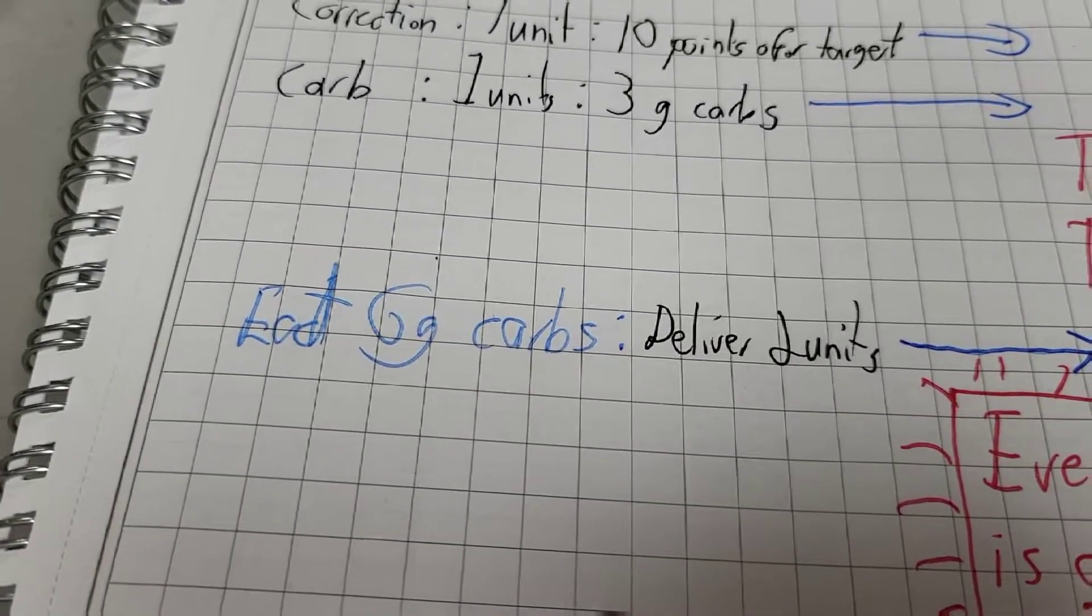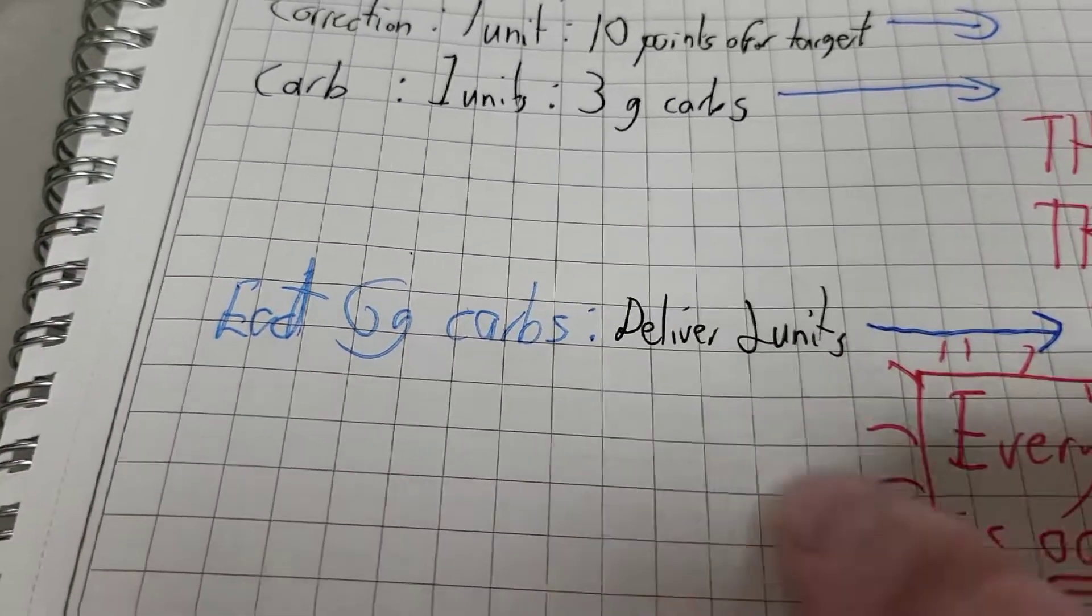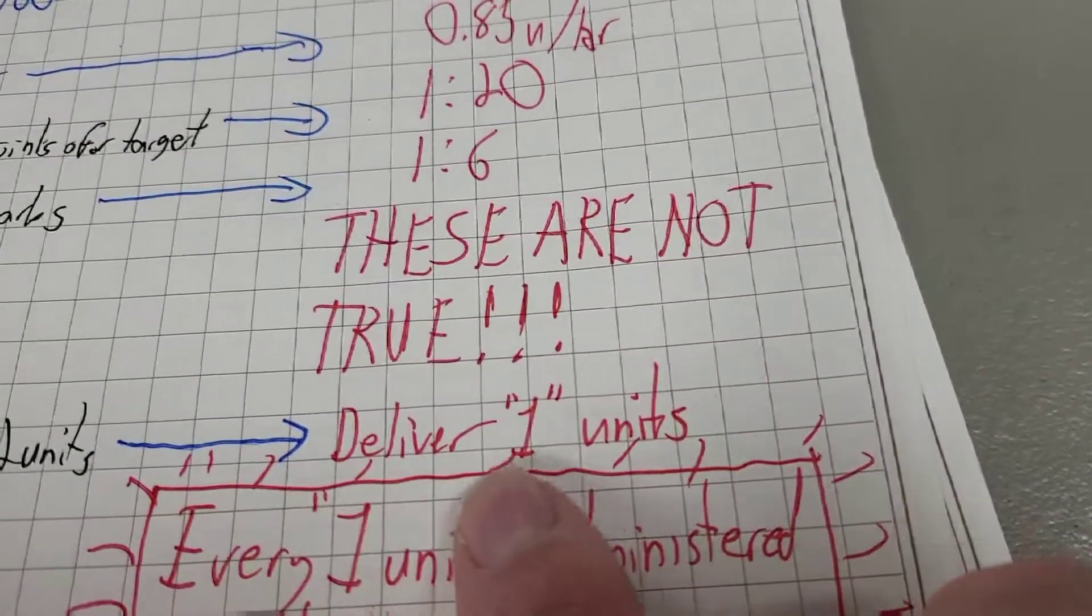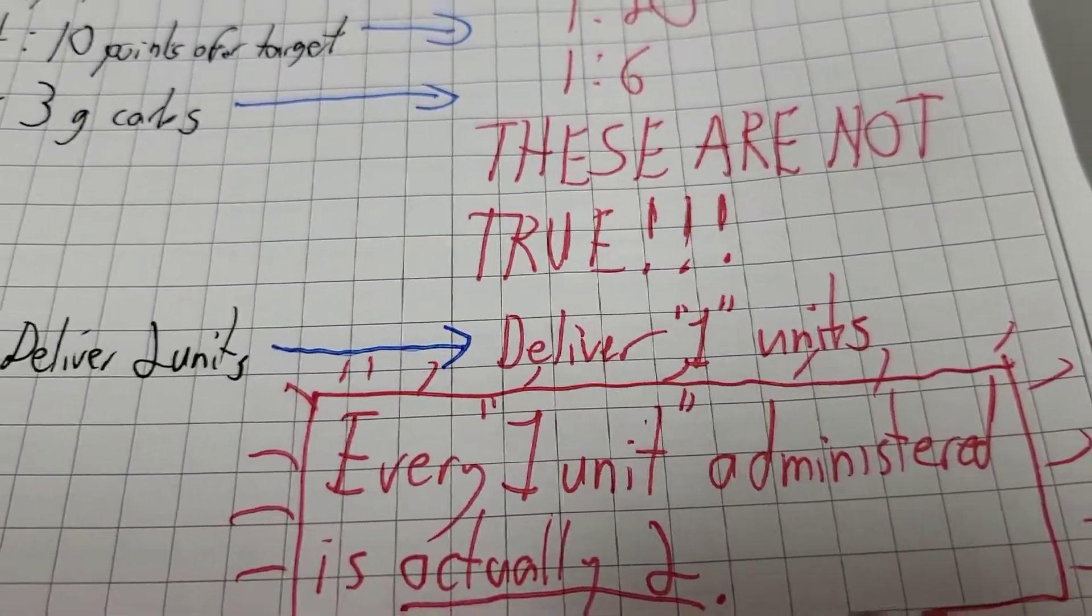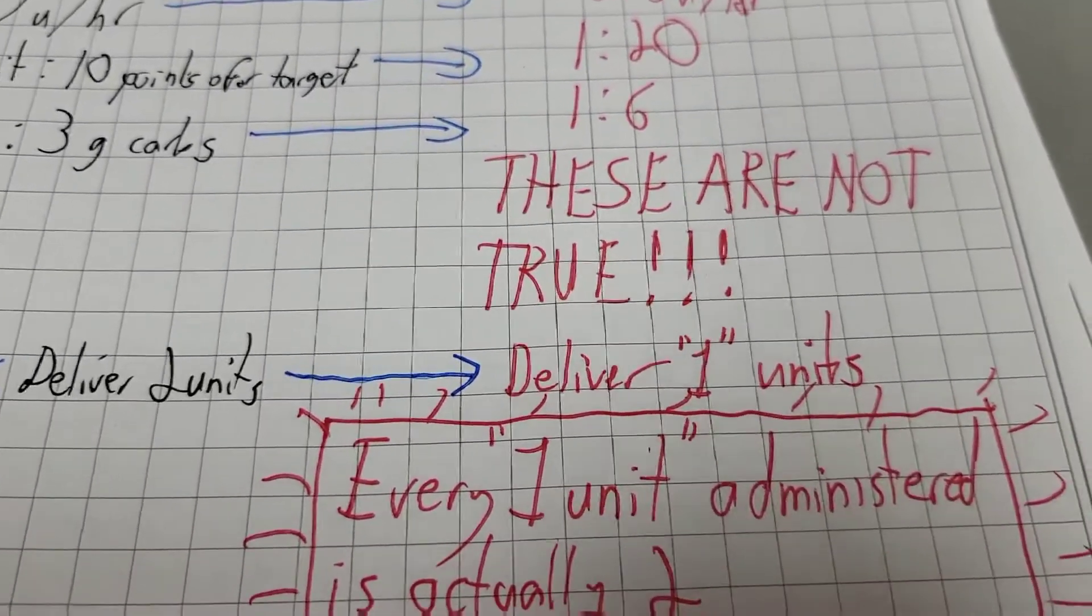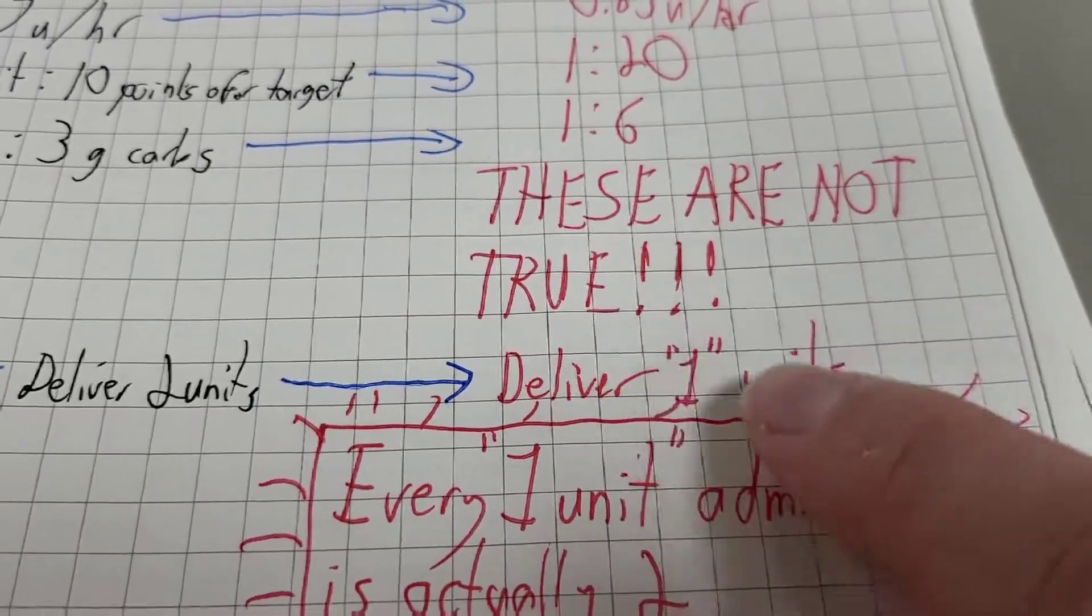If I eat six grams of carbs, for example, using U100, I would deliver two units. Using 200, I deliver one unit, but it's not actually one unit. It is actually two units. The pump just calls it one unit because the pump doesn't understand U200.